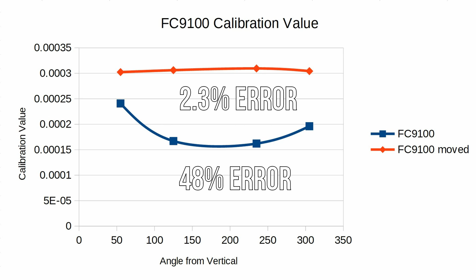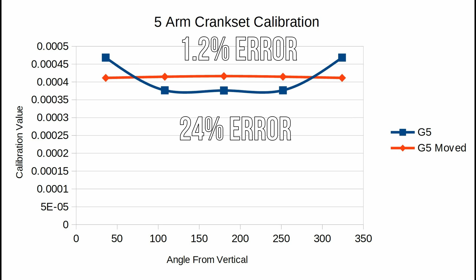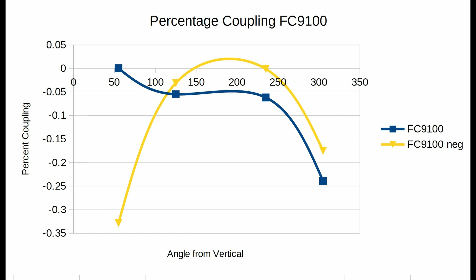When we look at the 5-arm, when it's really close to those spider arms, there's 24% error in the calibration, but when we move it a little bit further out, it's down to 1.2. And that's much better. Realistically, that theoretical error turns into a much, much smaller number. But when we talk about the coupling again, this is the percentage coupling, and sorry, the scale is not actually in percentage, so 0.1 is actually 10%. You're seeing some huge numbers here. The forward torque in the blue starts pretty flat around 5%, but between 0 and -20, near that -20, it gets near those forward torque dead zones in the vertical. But the negative torque too is actually negative. So no matter what you do, it causes this thing to read down, and that seems to be the big error.